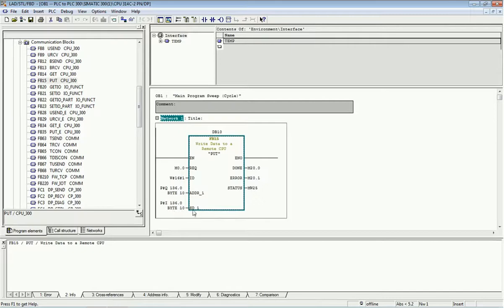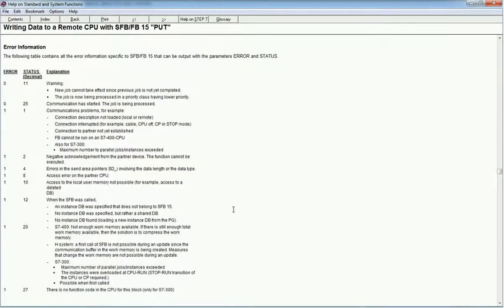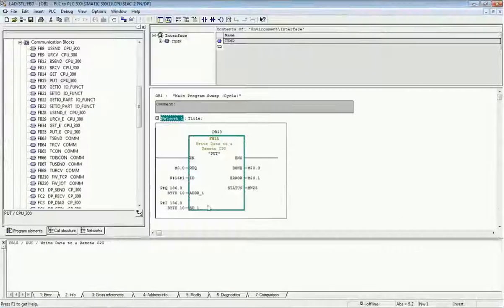In the PUT block I want to send 10 bytes of data starting from I136.0, and that data will be stored in Q136.0 for a total of 10 bytes. This is the standard format for sending and receiving data. On the right side you will get the Done, Error, and Status bits. If any error occurs you will get an error code, and from that code you can identify the exact diagnosis or troubleshooting needed.